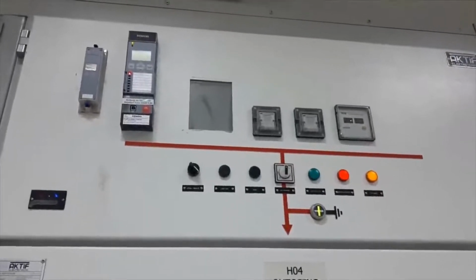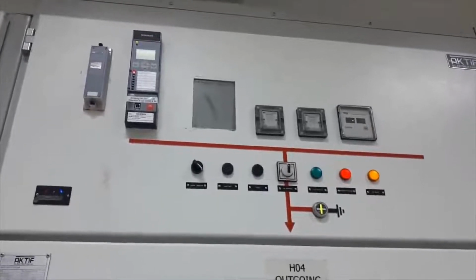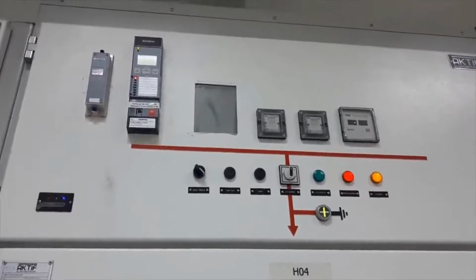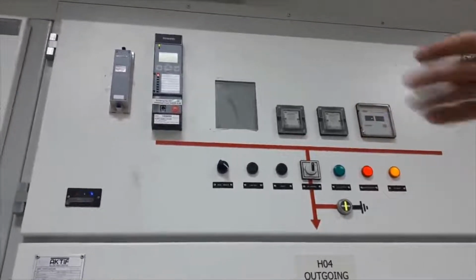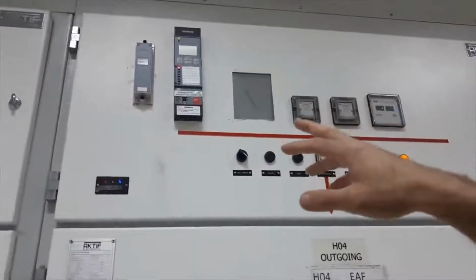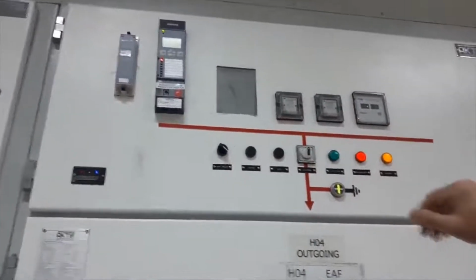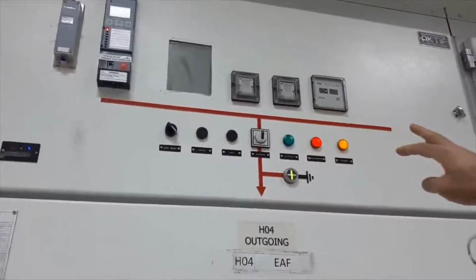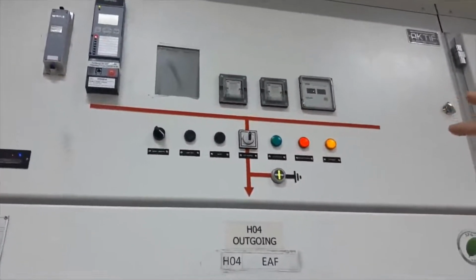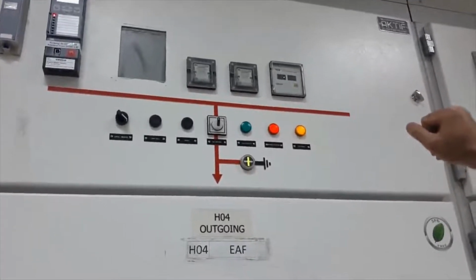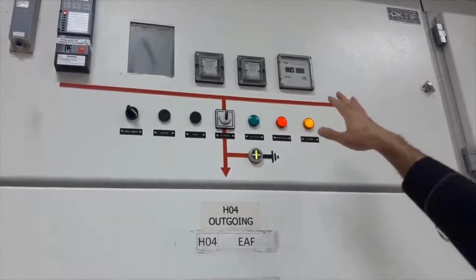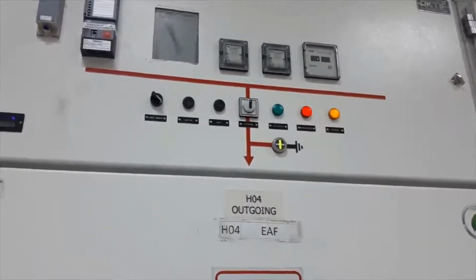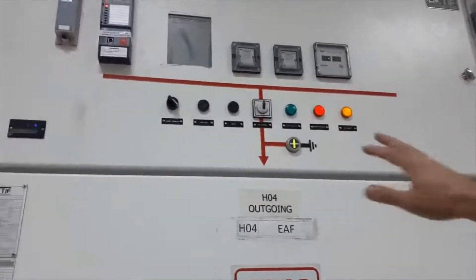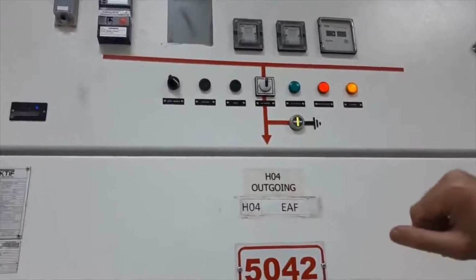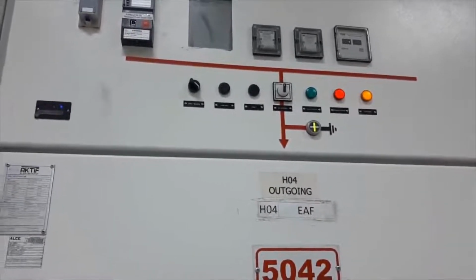So I will explain to you the equipment mounted on one of the outgoings. Up there is located the Siemens relay, model 7SJ80. Next to it is the test box, which is related to the relay. These two that are next to each other are lockout relays. This is TCS or Trip Circuit Supervision relay. This is the discrepancy switch by which we can disconnect or connect the feeder.